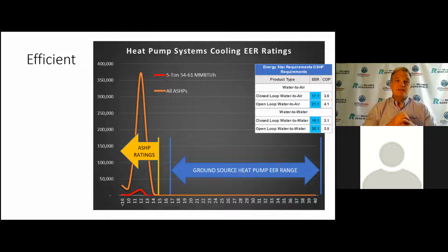To put that in context, my company and most geothermal companies don't sell any heat pumps below 17 EER. They just don't sell them. Most of ours are in the 32 to 40 range EER, so typically double or triple the efficiency of heating and cooling compared to air source. You can see some numbers in the upper right. Energy Star minimum is 17.1 for a ground source heat pump. We don't make anything that doesn't meet Energy Star Tier 3, with a COP of 3.6.